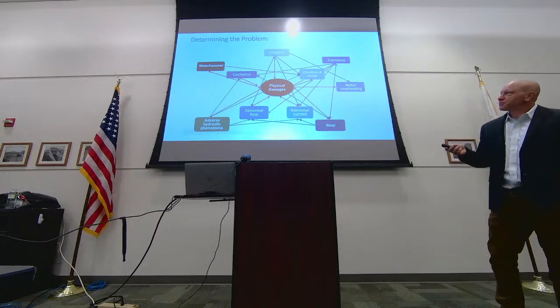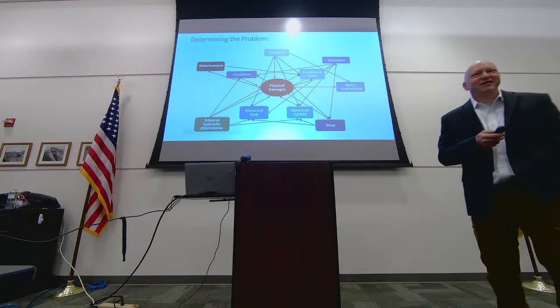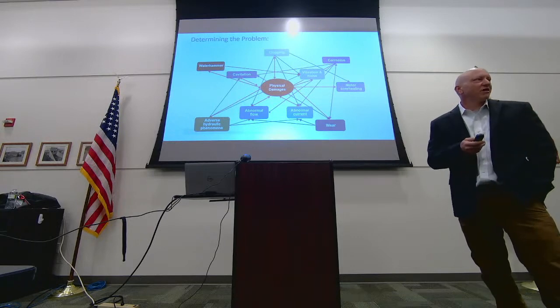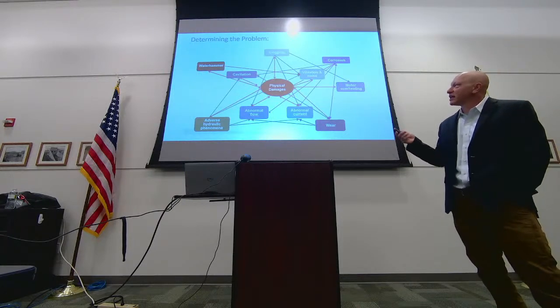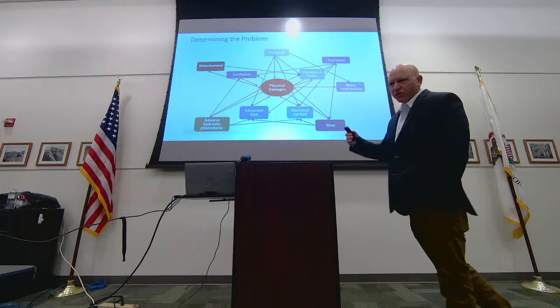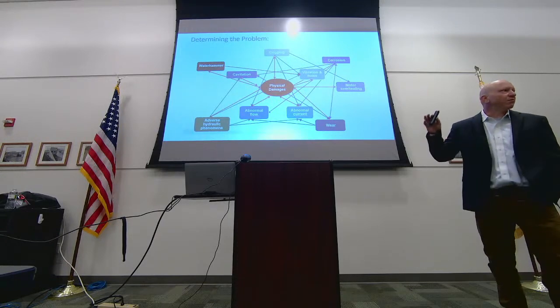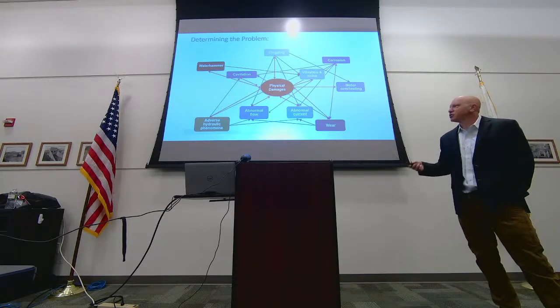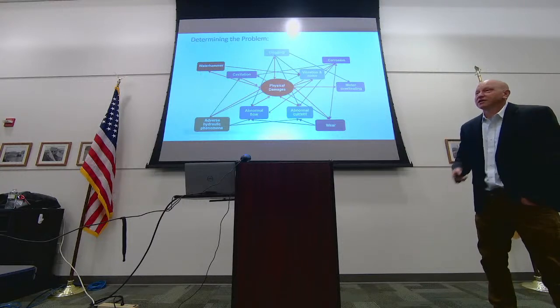Determining the problem. So you call me up and it's 3:30 in the afternoon on a Friday, and says, John, my pump keeps tripping out. It's overheating. Something's going on. And we go from there. I don't think this is a far cry from reality at all. Most of the time, the thing that called me out to a lift station in the first place, be it a noise or an overtemp or some type of alarm, ends up being a symptom, but not the problem. Noise is tied to vibration, which may be tied to cavitation, which may be tied to clogging, which may be tied to wear. Everything is all hooked together.